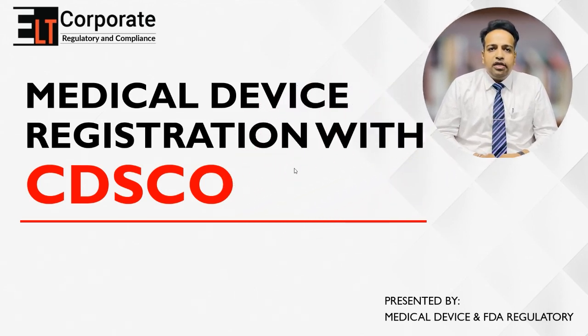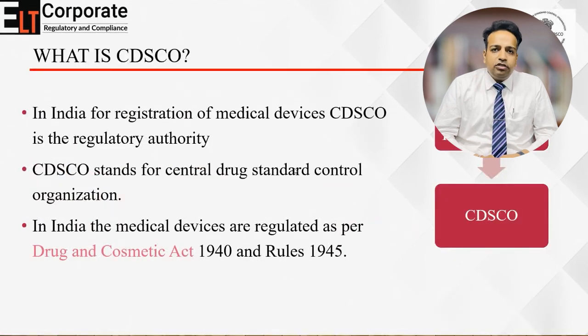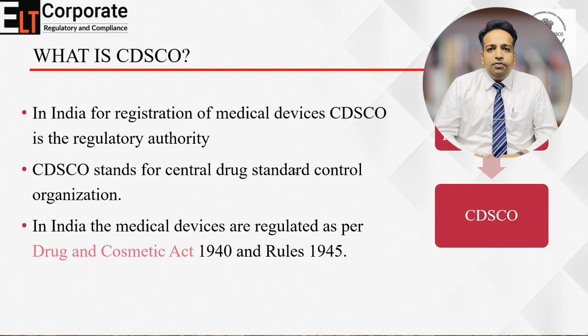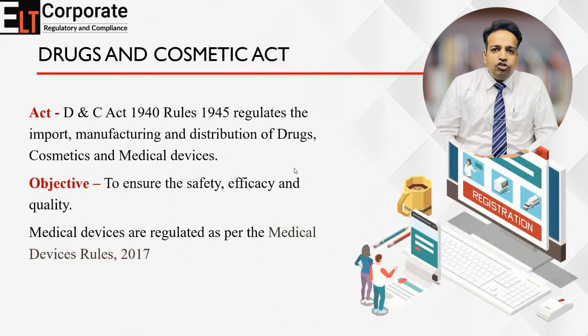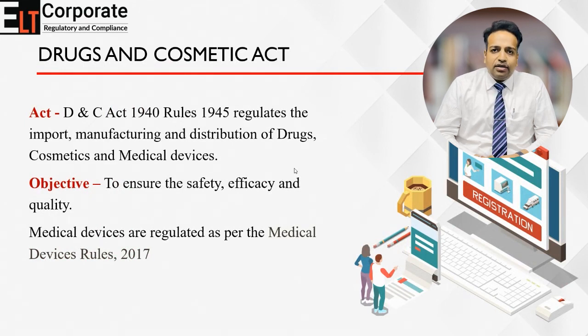In this video we will talk about how to register a medical device with CDSCO. CDSCO is an apex body in India which is responsible for the grant of licenses for medical device manufacturers and importers. The medical device industry is regulated under the Drugs and Cosmetics Act, and under the powers vested with the central government, the government has enacted Medical Device Rules 2017.